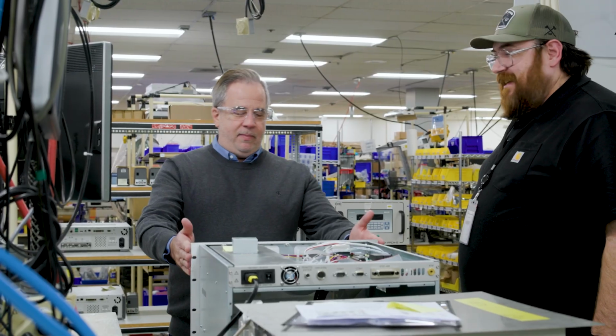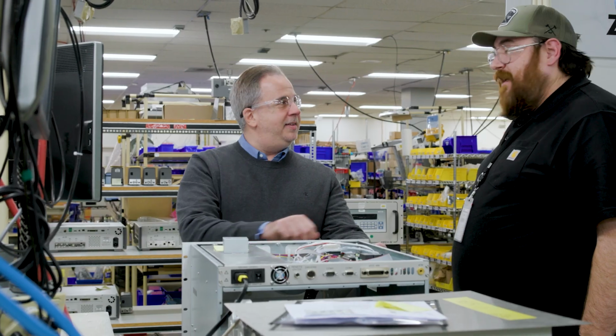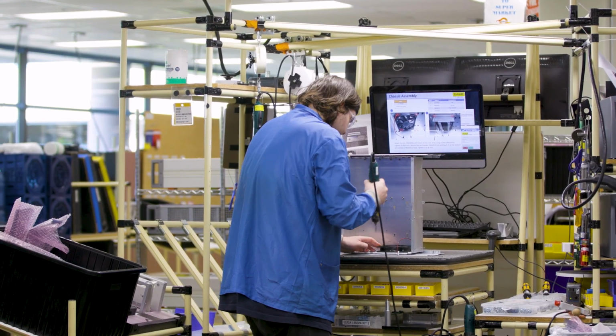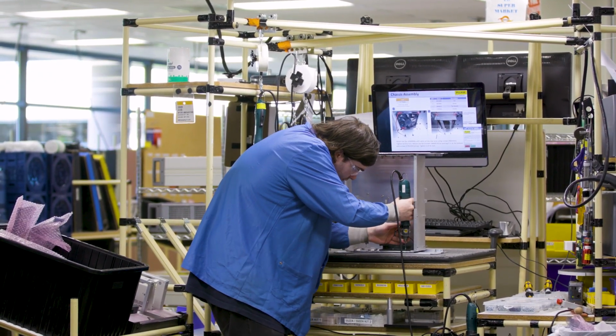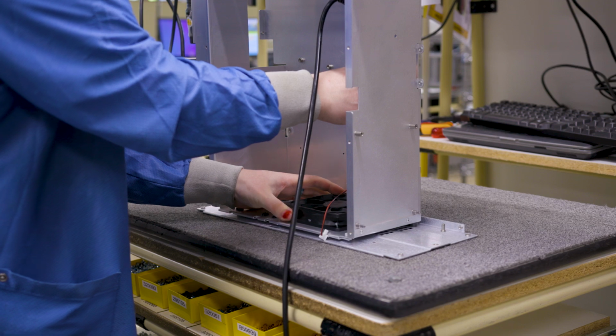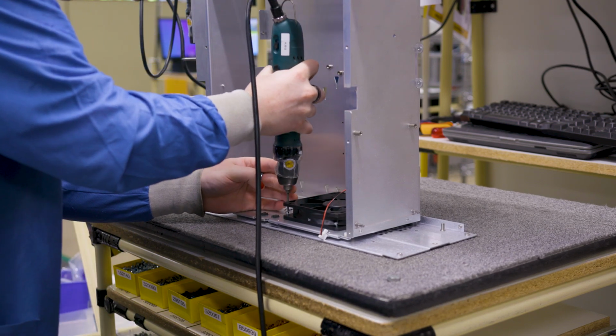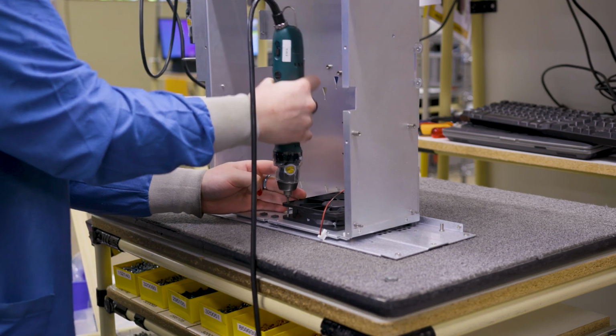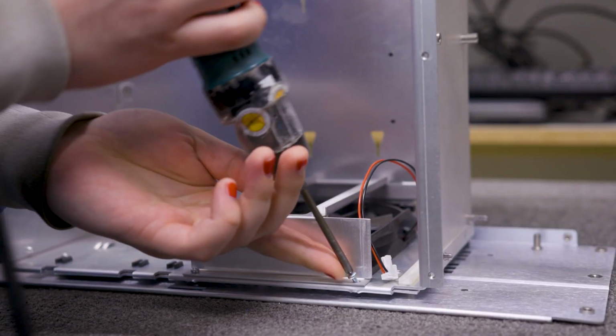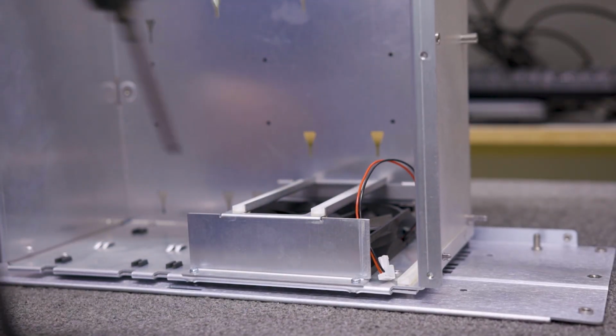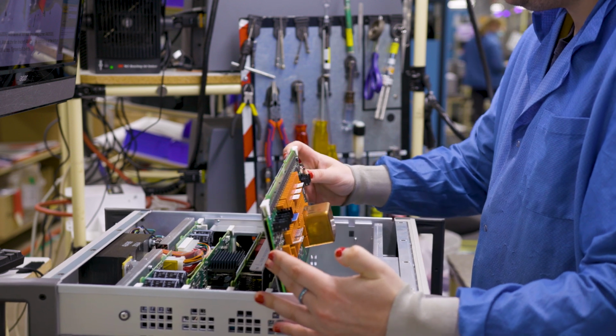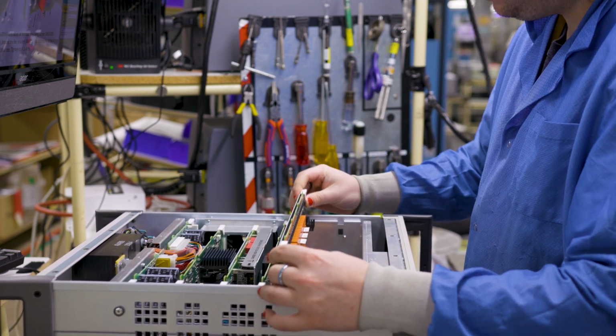The reason it's important for us to be at every step within the calibration process is because metrological traceability is the ability to trace a measurement and the error or uncertainty around that individual measurement up through a series of comparisons or calibrations of lower uncertainty and higher accuracy until we get to the realization of an SI unit. There are 7 SI units that all measurements in the universe are comprised of, one or more of those 7, and we want every measurement to be able to be traced back to one or more of those 7 SI units.